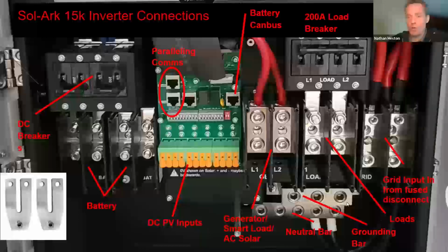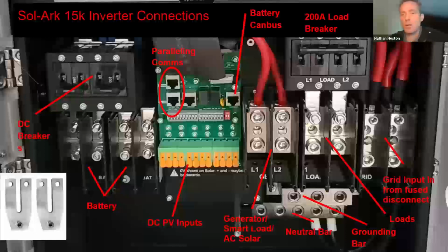And then, of course, on the bottom of our inverter, we've got our neutral bar and then our grounding bar. Keep in mind that the neutral ground bond is going to come in at the service disconnect. So we do separate the neutral and the grounding bar here in the inverter. The loads port here is shown, and you've got a breaker there to shut off your main loads panel.